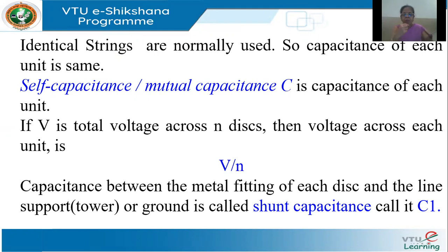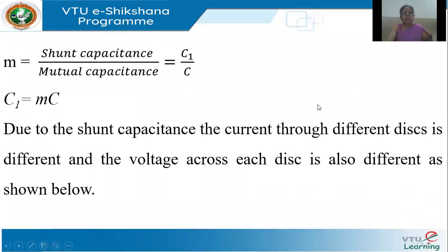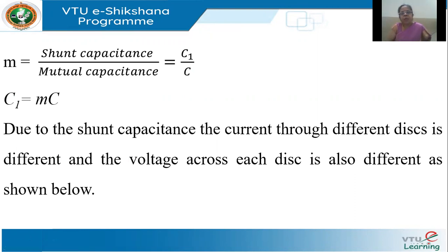Every disk has a metal fitting, so there will be a capacitance between this metal fitting and the support tower which is grounded. This is called the shunt capacitance. Let us assume the ratio of the shunt capacitance C1 to C is denoted by m. So my shunt capacitance is m times the self or mutual capacitance. The problem with the shunt capacitance is that it will create different voltages across each disk, even though all the disks are identical.